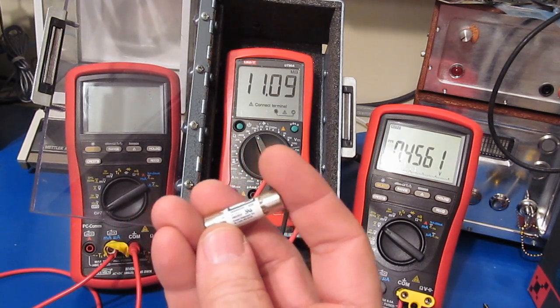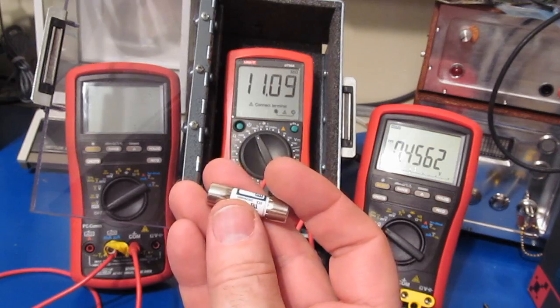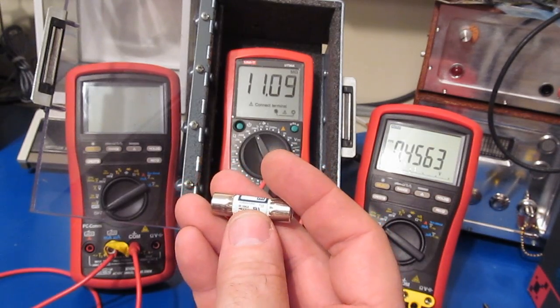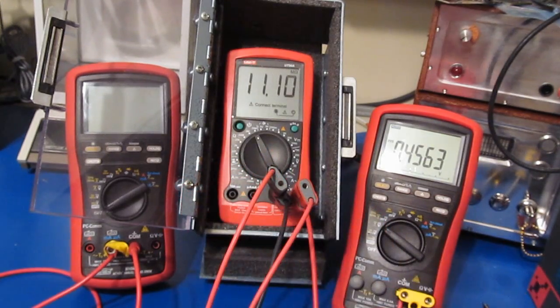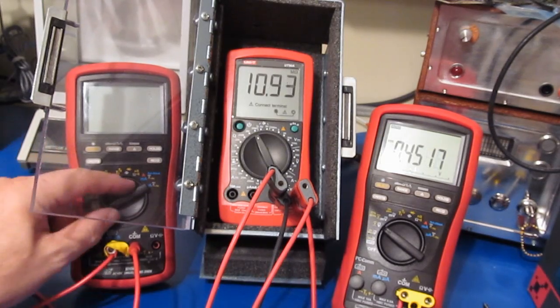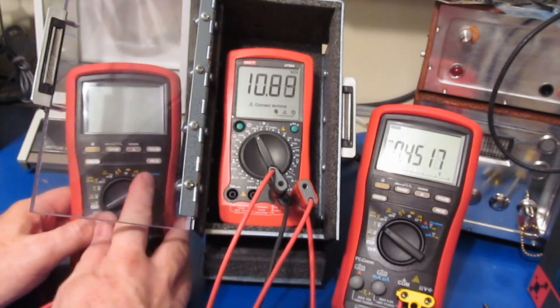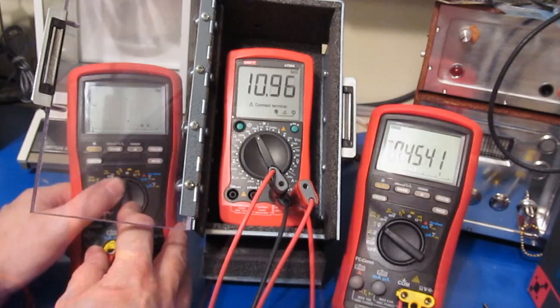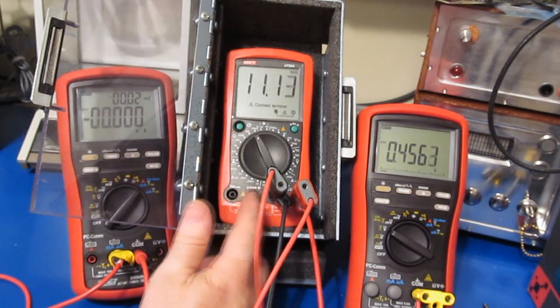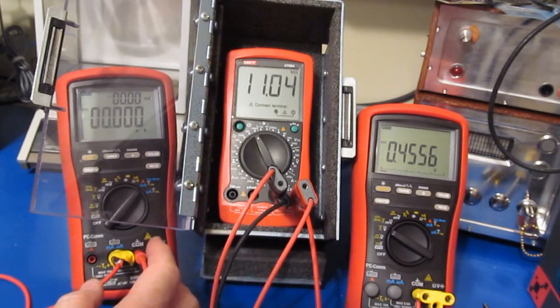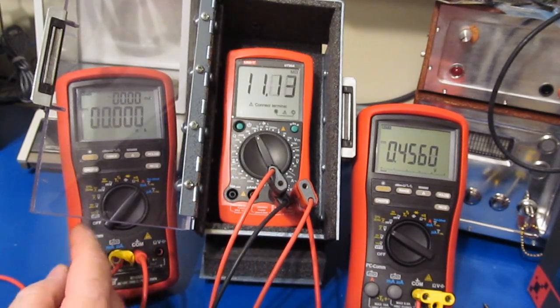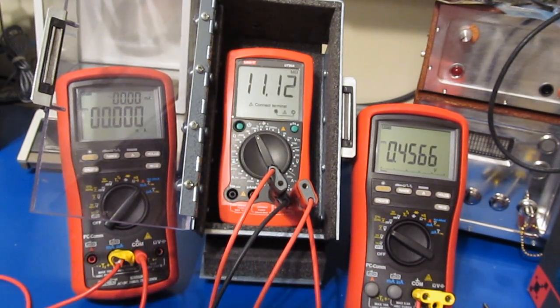Again, these fuses here are rated for 440 milliamps. They're 1000 volt AC/DC rated at 10 kA break current. I have, I think, 3 of those left, so hopefully we won't burn another one up. But unfortunately, if the meter arcs, it's going to draw a fair amount of current, which will either blow the meter's fuse or the one in line with the power supply.